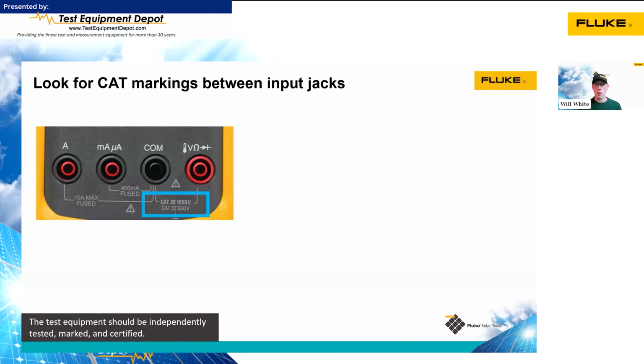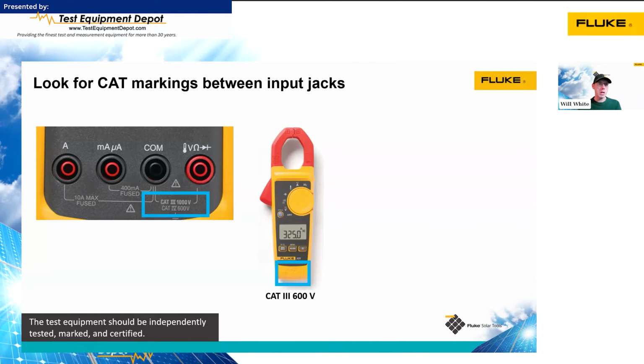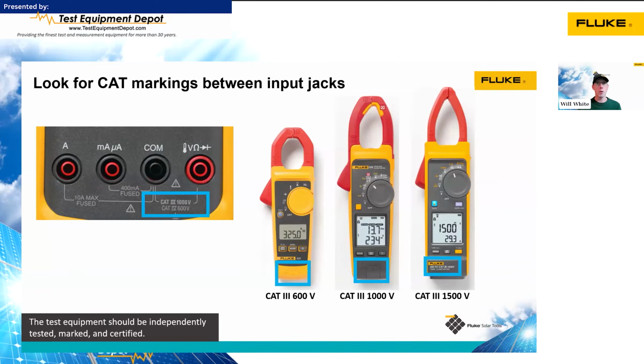We have a new multimeter coming out in a couple of months, the 283 multimeter, which is category 3, 1500 volt, category 4, 1000 volt rated. So that's good for those 800 volt systems. So clamp meters, same thing, category rating and voltage right on them. Here we have a series of 3 different meters, the 325 clamp meter on the left, the 378 clamp meter in the middle, and the 393 clamp meter on the right. It's all category 3 tools, but they go from 600 to 1000 to 1500 volts. And the scale of these pictures are relatively similar to their physical size. As the category and voltage rating goes up, the physical size of the meter gets bigger. And that adds additional safety factors at that higher voltage level.